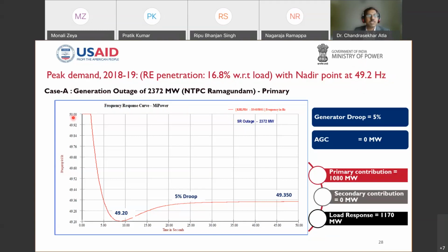Now what has happened here is, the frequency is 50 hertz, and a plant having 2,372 megawatt capacity, which is running at that instant, has gone out. If that happens, my frequency starts falling. The inertia of the other conventional generation determines this slope. If you have a good amount of inertia, it will come down like this. If you don't have much inertia in the system, it will come down like a straight line. With the availability of inertia, it has come here.